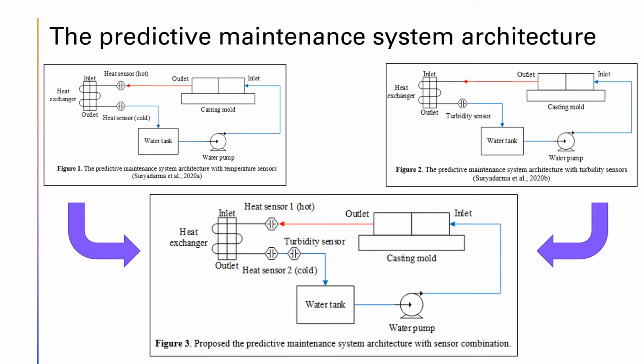The water that comes out of the mold outlet is then read by a temperature sensor and enters the heat exchanger. And then the difference in temperature of the inlet and outlet of the heat exchanger is used to calculate the total heat transfer rate. And then for figure 2, here we show the predictive maintenance system architecture using a turbidity sensor. This architecture uses one turbidity sensor to monitor water turbidity, which will be used to determine predictive maintenance. It does not require further calculation. Turbidity data is directly used in the machine learning algorithm to predict.